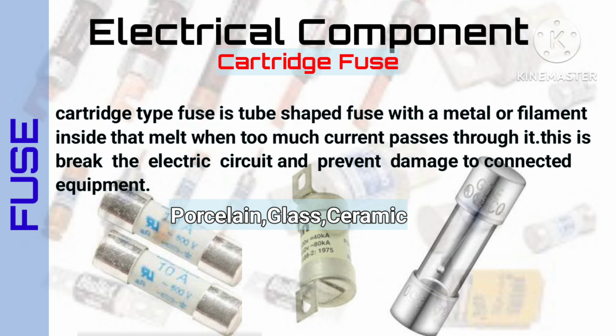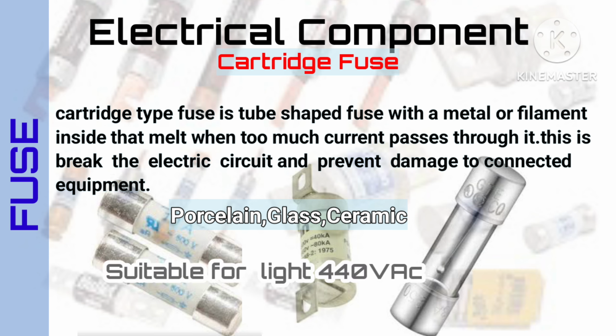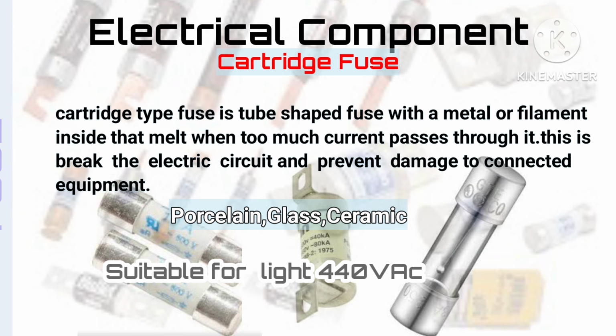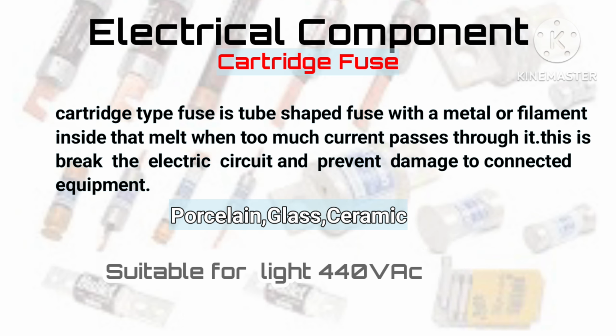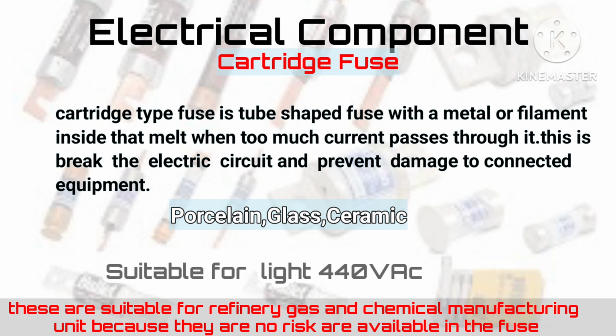Advantages of the cartridge fuse: the fuse elements are protected in a tube, so there is no risk of sparking or arcing. It operates faster than a rewirable fuse during a fault condition. It is used in applications of higher reliability and is more compatible with high voltage. It is suitable where petrol, gas, or chemicals are used or made.